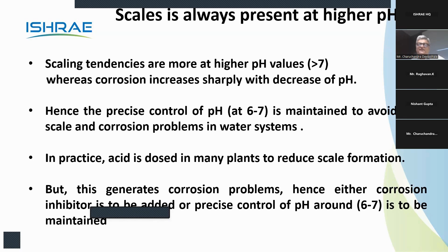In practice, acid is dosed in many plants to reduce scale formation, but this acid dosing has to be very calculated, and it should be done with experts whenever they are available, since this can generate corrosion problems. Either a corrosion inhibitor is to be added, or precise control of pH around 6 to 7 is to be maintained so that no acidity develops in the system.